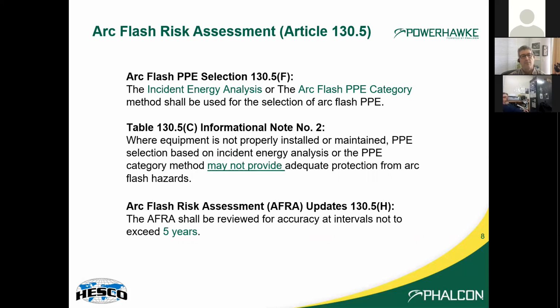That's why it's so important that, going forward, equipment needs to be maintained. The arc flash risk assessment assumes equipment is going to operate the way it was installed and intended to operate. If it hasn't been maintained in 5, 10, 15 or more years, it is certainly not going to provide the level of protection to the employees and the system that it was intended. So maintenance is a big issue.